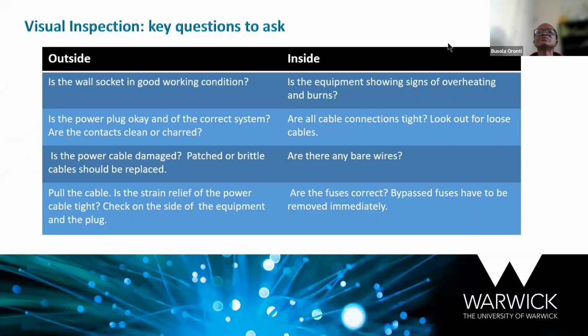So when we're talking about visual inspection, we're talking about looking at the outside of the medical equipment and then looking at the inside, if that is allowed, if that's permitted. So when we're talking about the outside inspection, look at the wall sockets. Are they in good working condition? Is the power plug okay? And of the correct system, because you can have the American system and then the British system. We use the British system in Nigeria. Are the contacts clean, or are they charred? So these are things to look at.